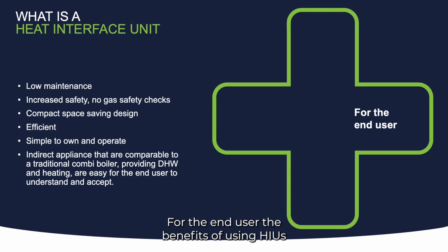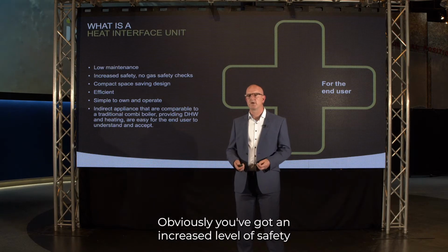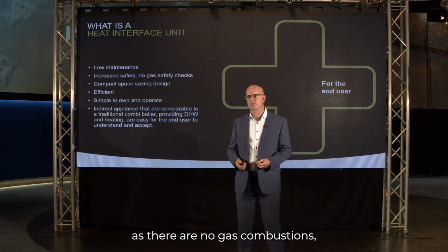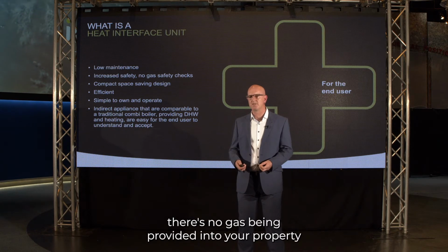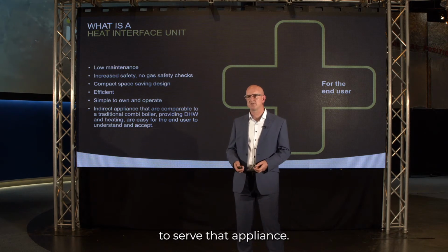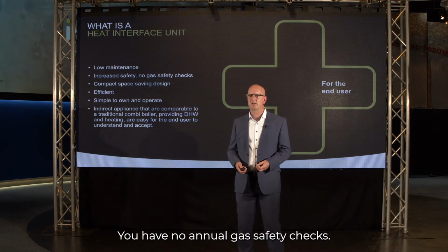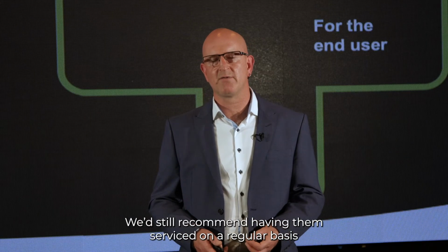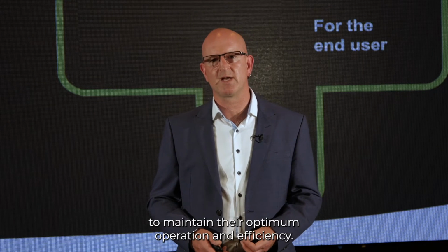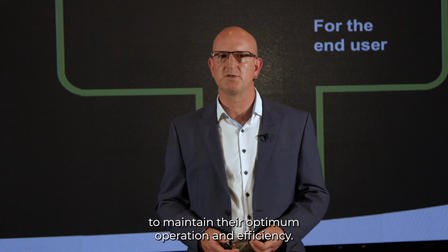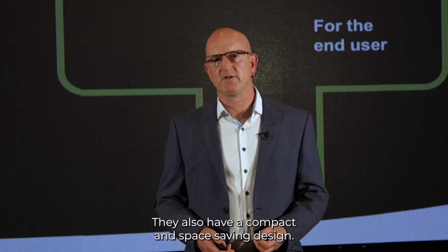For the end user, the benefits of using HIUs is they're a relatively low maintenance appliance. Obviously you've got an increased level of safety as there is no gas combustion, there's no gas being provided into your property to serve that appliance. You have no annual gas safety checks. You'd still recommend having them serviced on a regular basis to maintain their optimum operation and efficiency. They also have a compact and space-saving design.